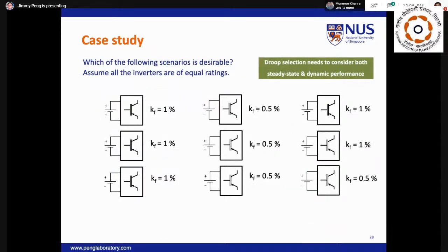Let's have a look at a simple case study consisting of 3 inverters with various frequency Droop settings. The question we should ask is, which of the following scenarios will generate a more desirable performance in terms of response speed and stability? Now, all the inverters in the first and second scenarios have the same Droop gains, where the first scenario on the left-hand side is 1%, and the second scenario in the center is 0.5% Droop gains. This basically indicates that the inverters will be doing equal power sharing. On the other hand, the third scenario on the right-hand side introduces unequal power sharing, and this will introduce stress to one of the inverters, which is actually not a desirable attribute at steady state.